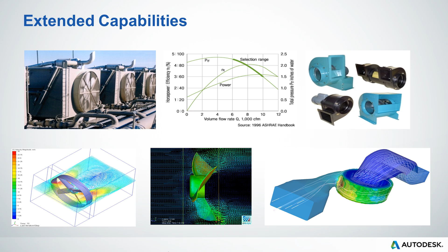With Autodesk Simulation CFD, the designer can simulate the airflow being driven through the fan by the rotation of the impeller. The designer can then look to measure the variation in flow rates as the pressure is varied in order to develop the performance and efficiency curves. At the same time, the designer can gain insight into how the fan behaves, not just in a test rig, but in a particular installation and how it interacts with the surrounding ducting and enclosures. The design of the fan blades and enclosures can be optimized to ensure a smooth delivery of air with a minimum of loss and the minimum of noise.